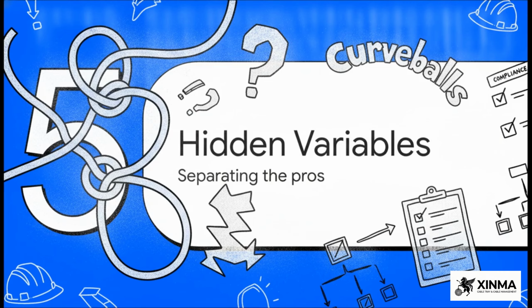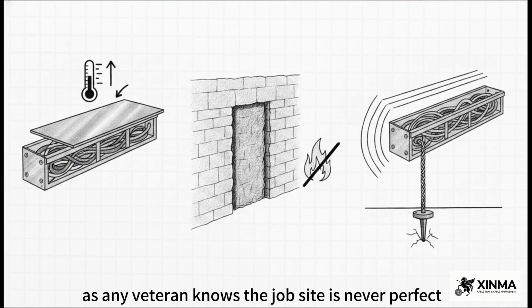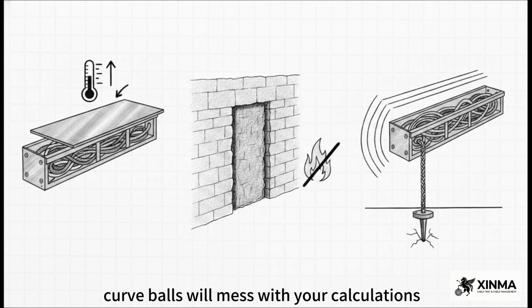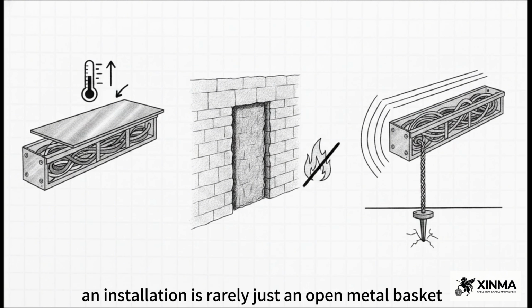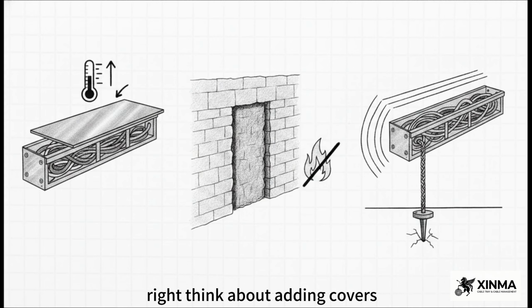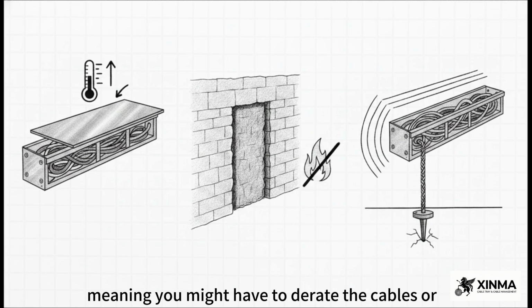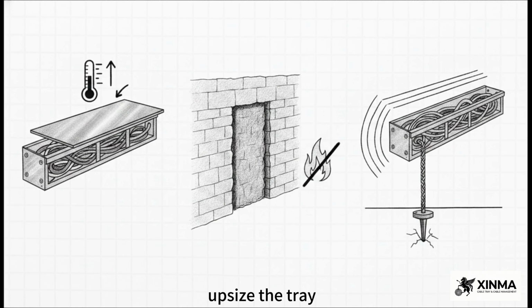Finally, Section 5, Hidden Variables and Compliance Standards. What separates the pros? As any veteran knows, the job site is never perfect. Even with a flawless plan, curveballs will mess with your calculations. An installation is rarely just an open metal basket, right? Think about adding covers. They protect cables from debris, sure, but they also trap heat, meaning you might have to derate the cables or upsize the tray.